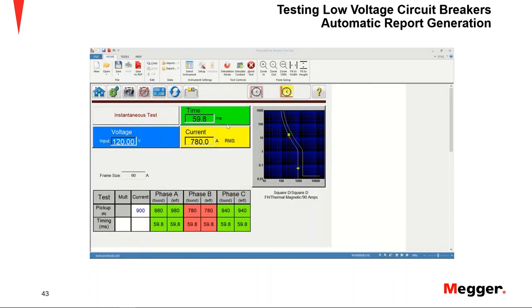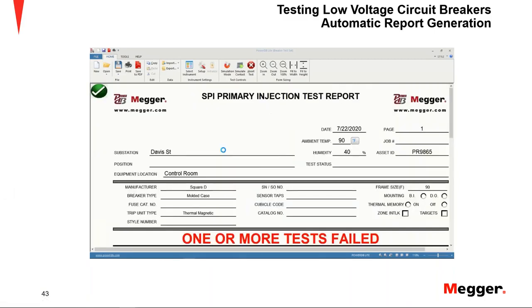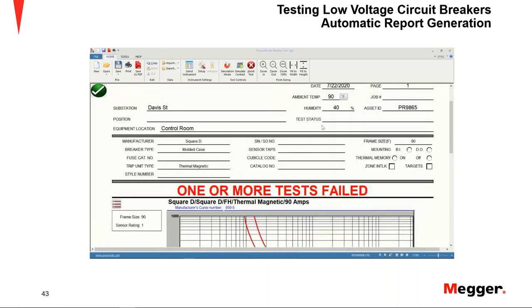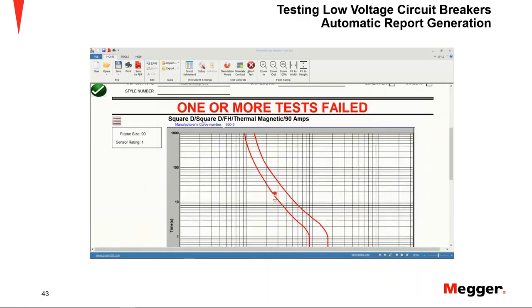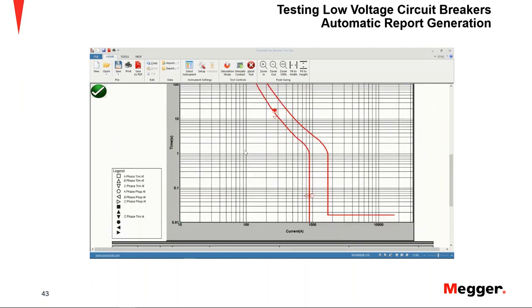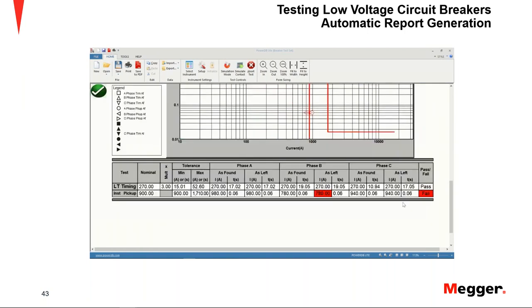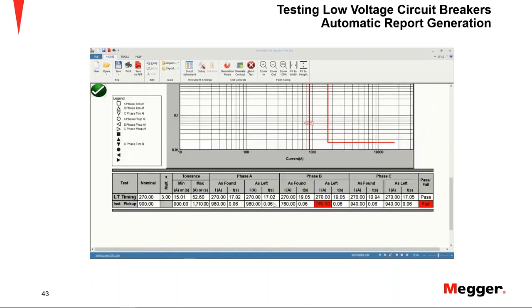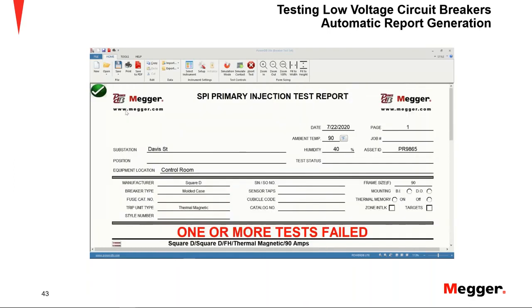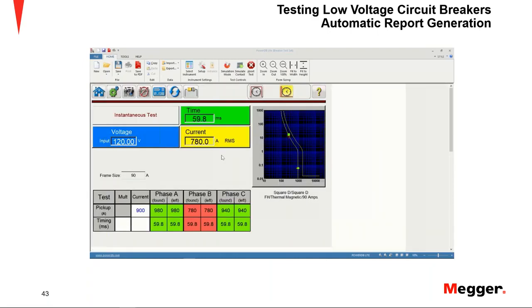To generate the report, it's as easy as to click this icon right here. So let's look at how that looks in the software, right? When clicking live, just a couple of seconds, the report is generated. Includes my identification that I filled out in the nameplate, the graph with the curve, again, so no more comparing with paper, and my numerical data in the table, highlighting the ones that failed, and I have that big indication in the top saying that something went wrong, something failed.